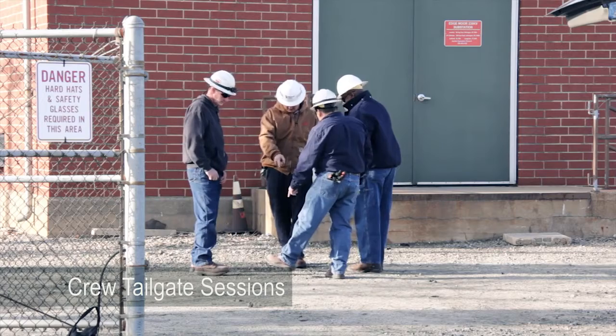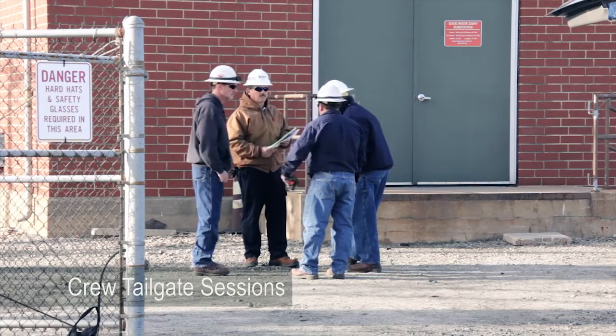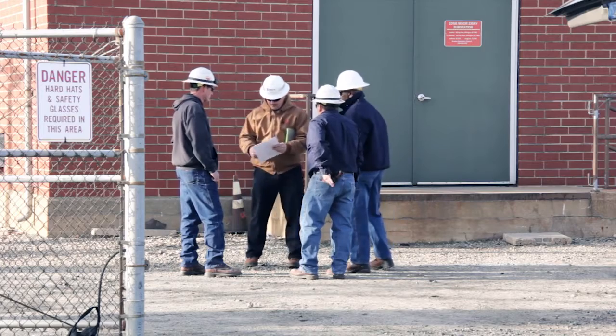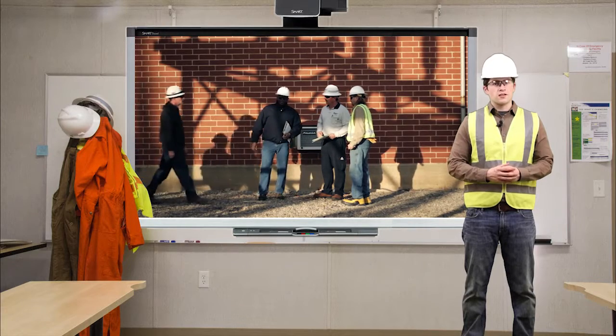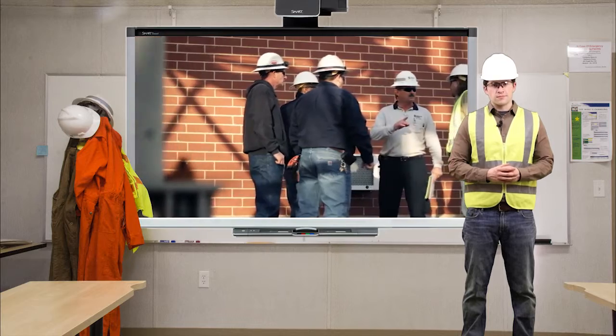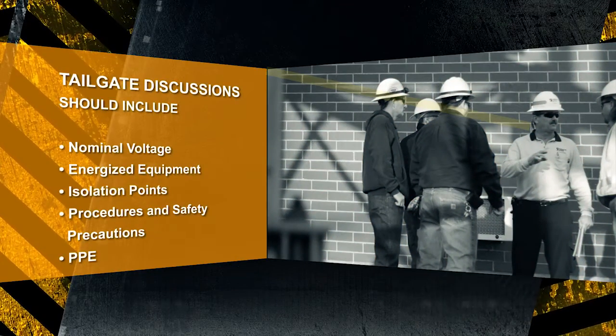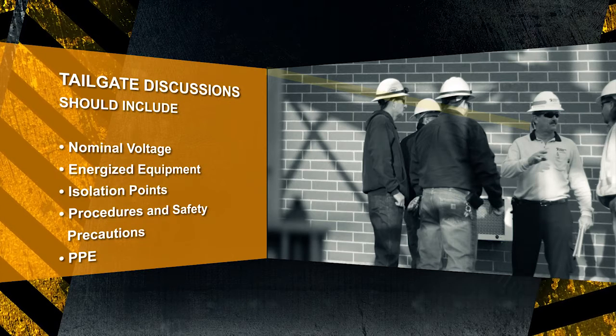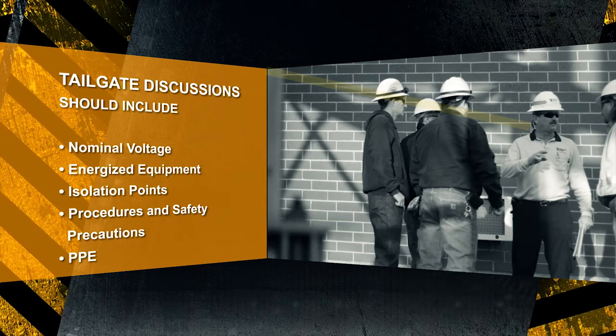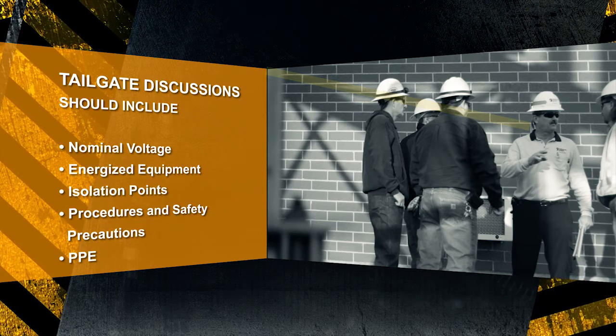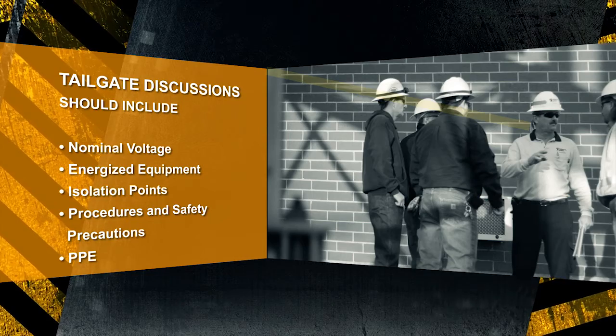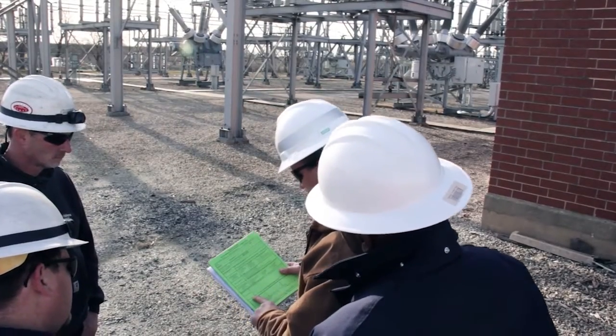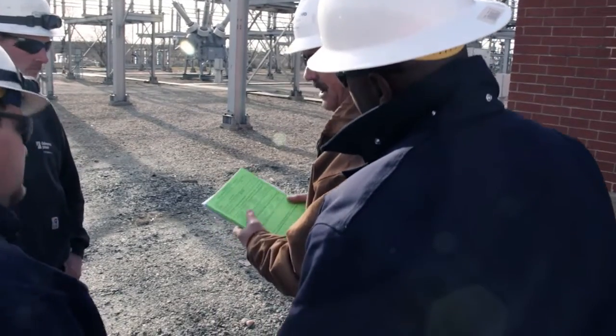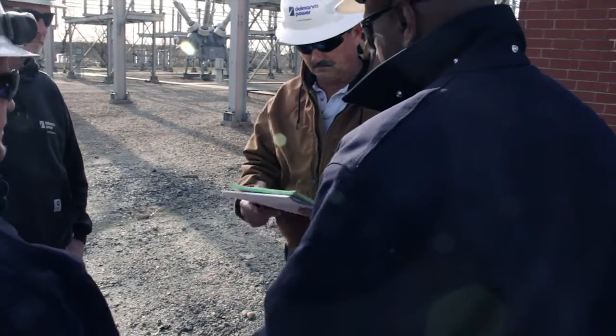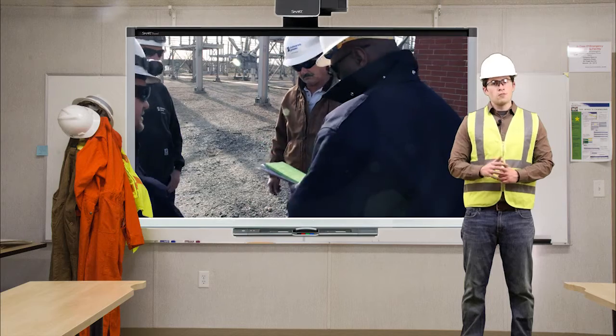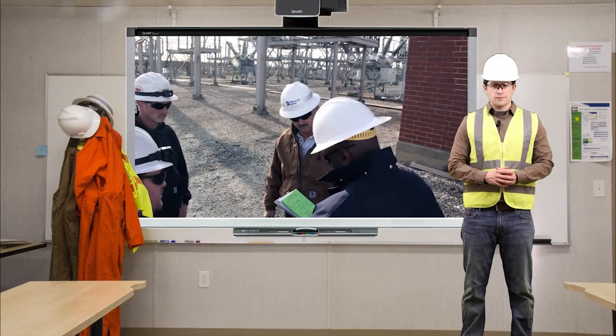Documented tailgate meetings are required by you or your team before the start of any job or at the beginning of each shift on site each day. A tailgate meeting is also required if conditions change or new personnel enter the site. Tailgate discussion should include nominal voltage within the yard, specifics on energized equipment, isolation points, specific work procedures, and precautions to ensure that you do the job safely, and required PPE for work. The contractor in charge of the project is responsible for documenting the tailgate meeting. If your company does not have a form, you may reference the PHI Tailgate Meeting Checklist form. All members of the contract team must participate in the tailgate.